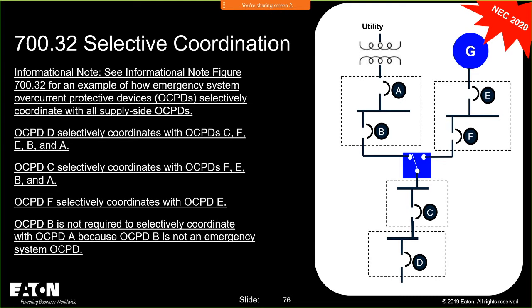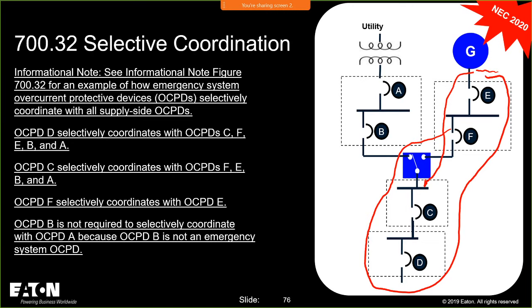The big debate has always been focused on these 2 devices. At least one of the big debates has been focused on those 2 devices, and whether or not they have to selectively coordinate with each other. Keep in mind, let's take Article 700 as an example. If I wanted to know what devices in this one-line diagram are a part of the emergency system, it would be devices E, F, C, and D. The requirements in Article 700 apply to everything on this life safety side of this equipment, everything down here. So that is where your life safety system resides. Devices A and B are outside of the purview of Article 700.